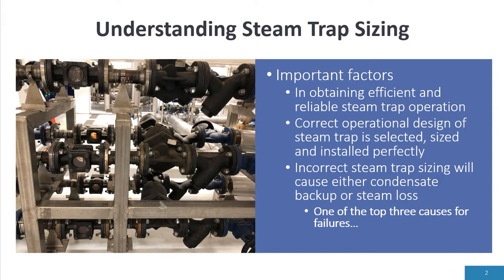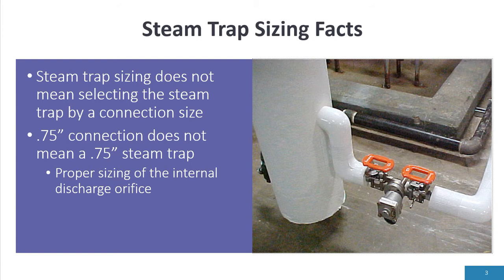Understanding steam trap sizing and its important factors. We need efficient, reliable steam trap operation, and that comes from proper sizing and correct operation — the design of the steam trap is selected, sized, and installed perfectly. Incorrect steam trap sizing will cause either condensate backup or steam loss. One of the main failures of steam traps is improper sizing. Steam trap sizing does not mean sizing the trap by connection size. A three-quarter inch connection doesn't mean a three-quarter inch steam trap — it's sizing the internal orifice of the steam trap, and that's what I want to talk about today.